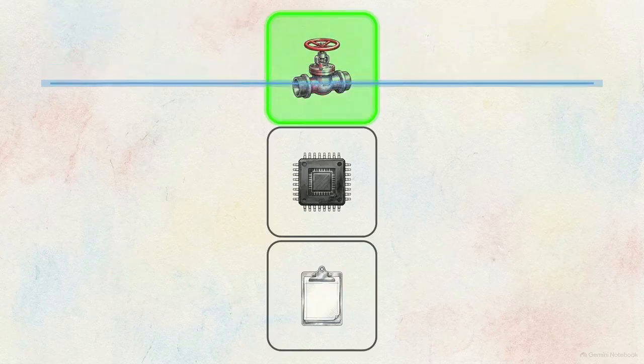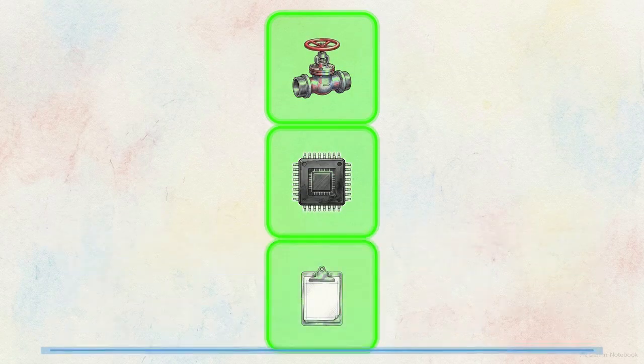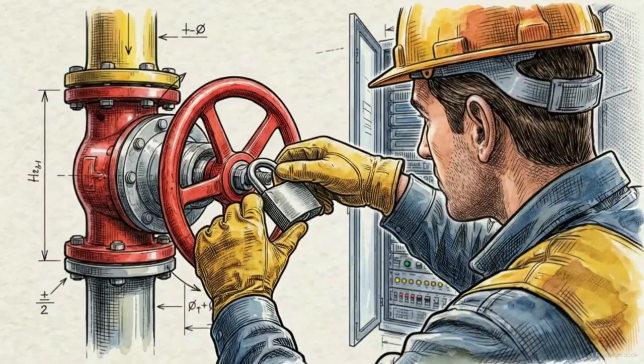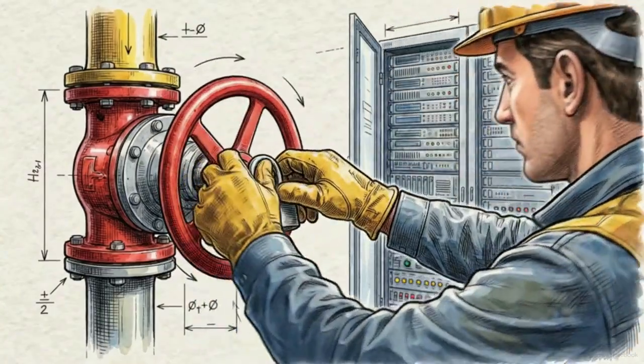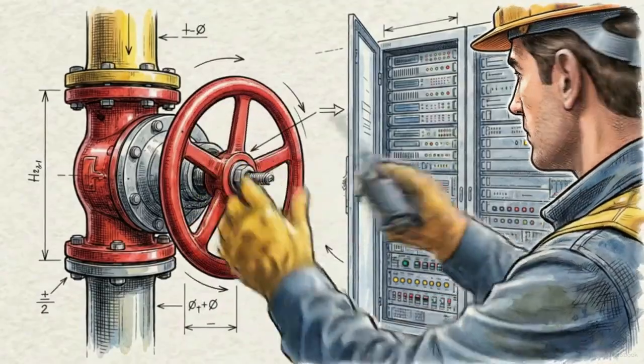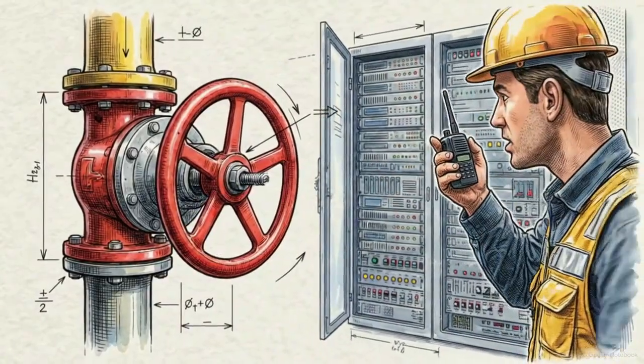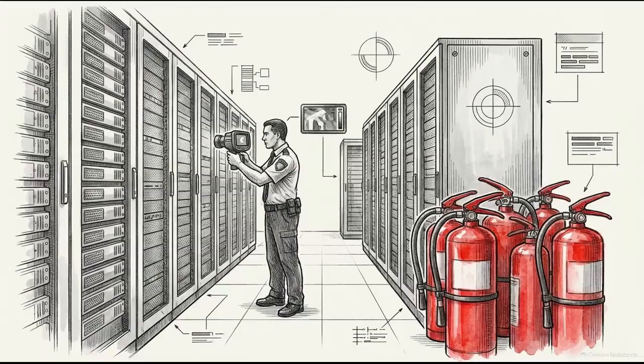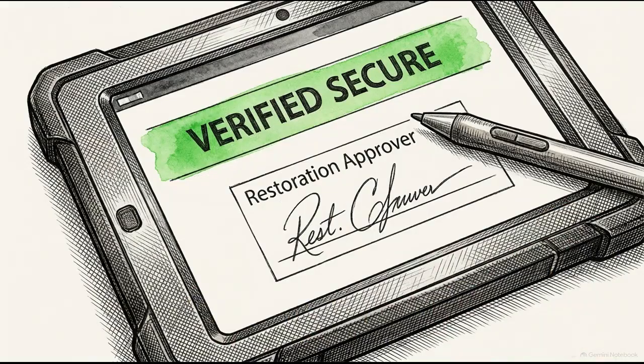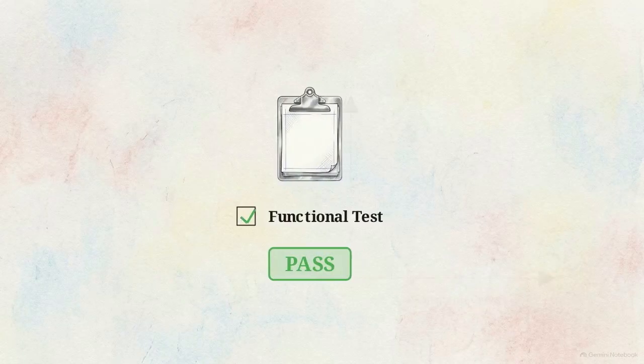Once work is finished, operators execute deterministic restoration. This protocol verifies that the physical valve state, the digital control logic, and the administrative records all perfectly align. The control sequence depends on the situation. While plant maintenance has pre-authorized boundaries, an emergency impairment requires rapid stabilization and immediate containment of secondary hazards. Whenever a Class A system is bypassed, operators must immediately deploy active fire watches and verify temporary protection to cover the gap. A system is functionally restored only when its performance is proven, and the result is digitally recorded by a named approver. Simple pass-fail checkboxes are an operational risk.